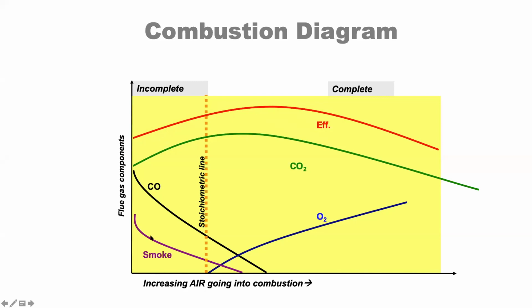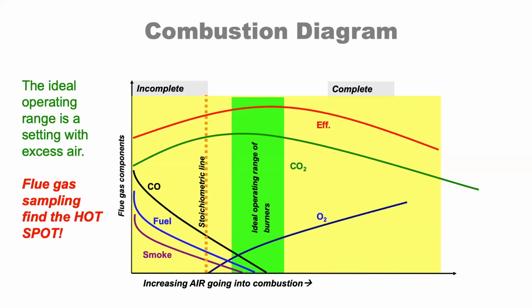You can also see if it's a oil burning or even propane, and sometimes natural gas, you can see smoke coming from these systems. The smoke amount, which is the raw carbon, does tend to decrease as you go towards higher amounts of oxygen, higher amounts of air in the system. And the good operating band would be this green bar in the center here, which is an operating with some excess air.